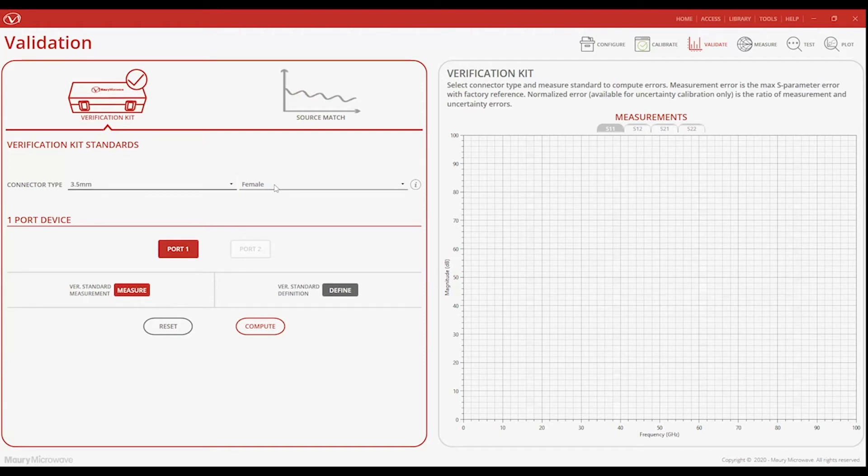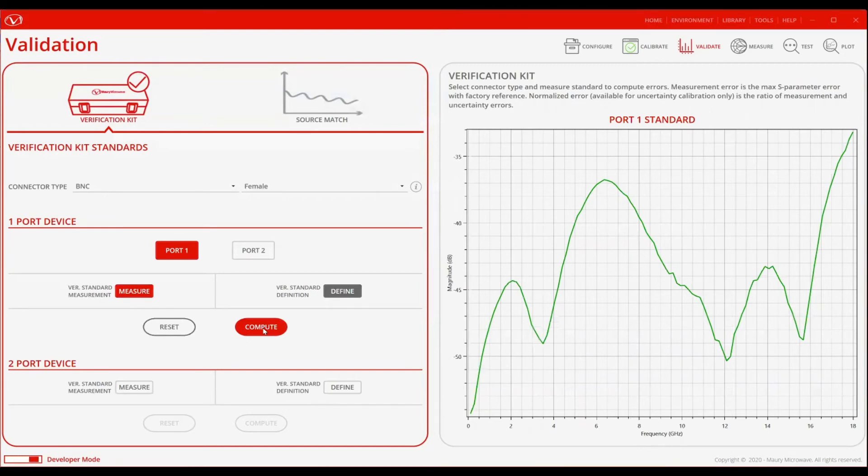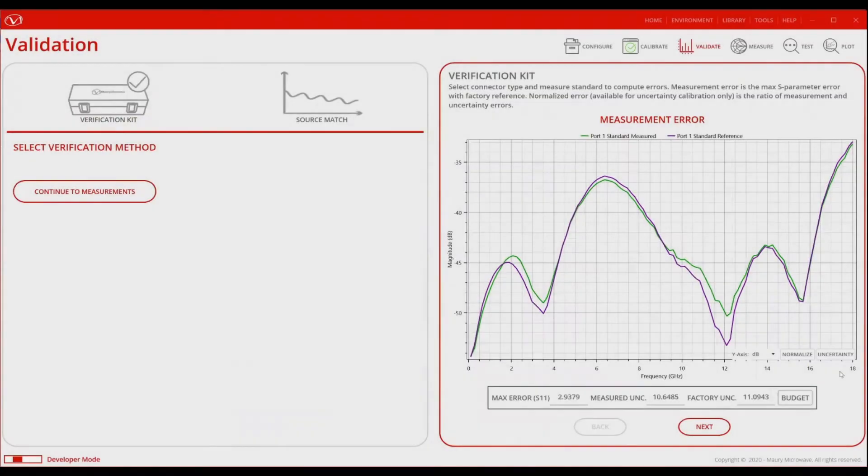We will then select the appropriate verification standard that best mimics our device under test, select the corresponding option in the software, and load the characterization data that is shipped with the kit. We will then connect the same standard to our newly calibrated VNA, and take a measurement to compare the results. The closer the two measurements overlap, the more valid our VNA calibration.